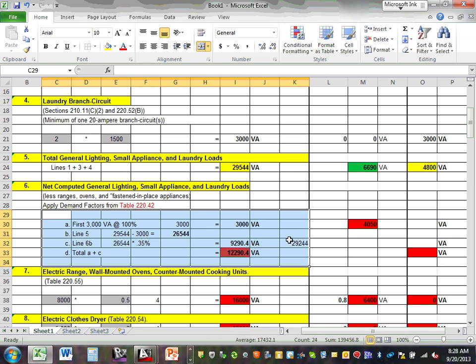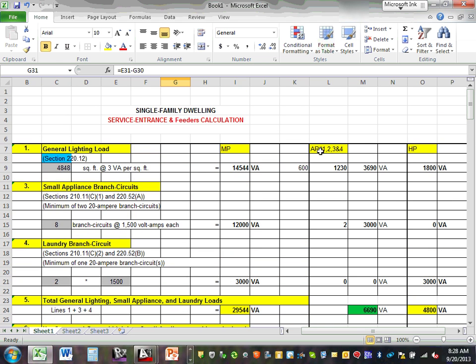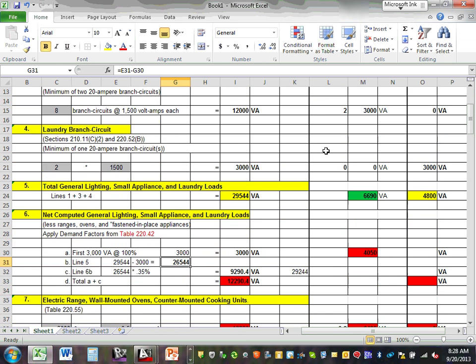It's really straightforward. The first 3, leave them alone. Anything higher than 3, cut by 0.35. That's how you do the math. If you look at the math, you subtract 3,000 from the total, which is this one, then multiply it by 0.35. That's for the whole building. I'm going to do the same thing for the apartment. Shall we do it for the apartment?